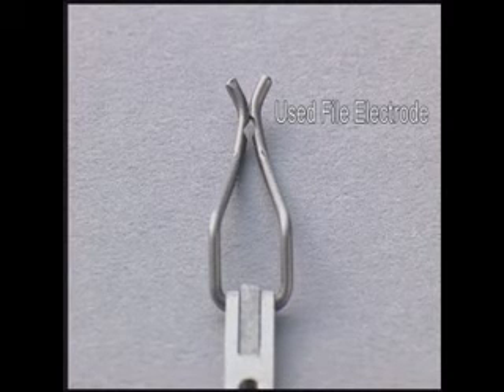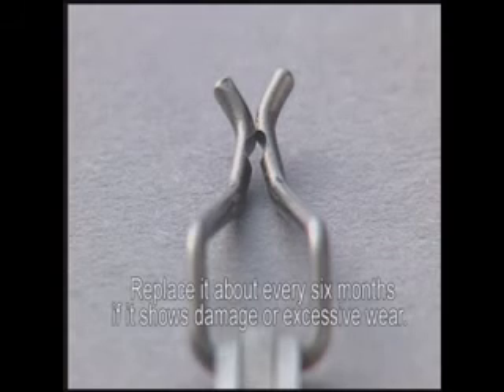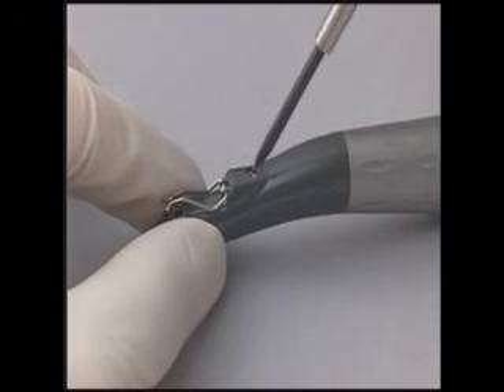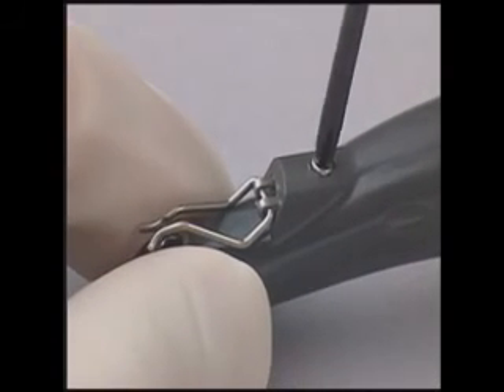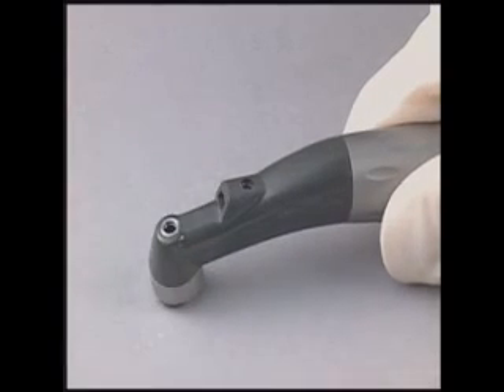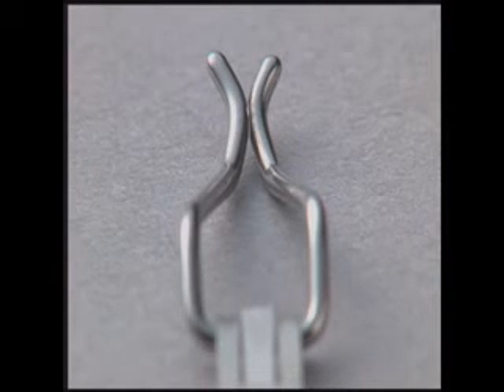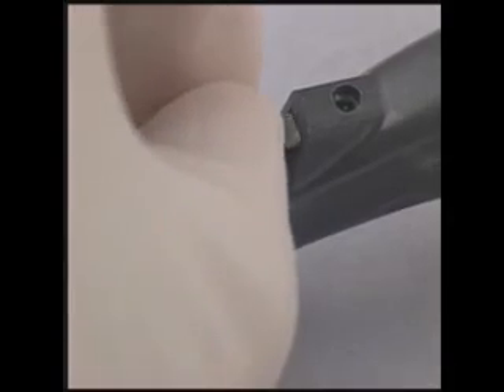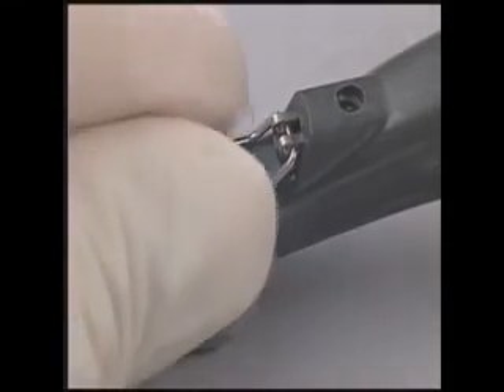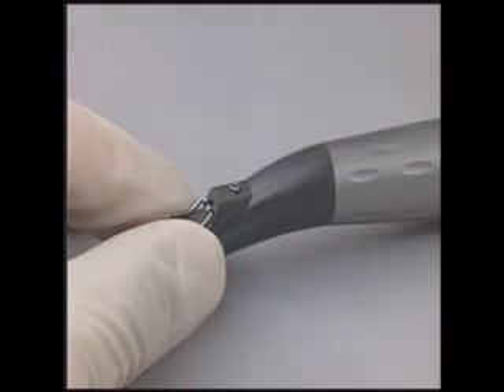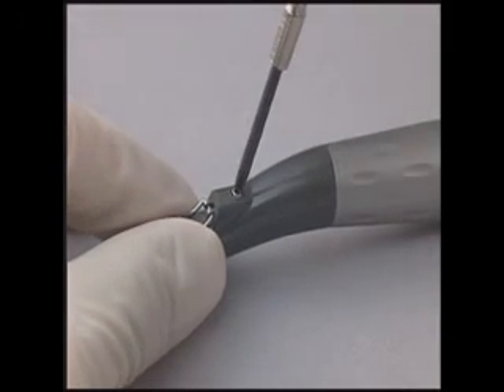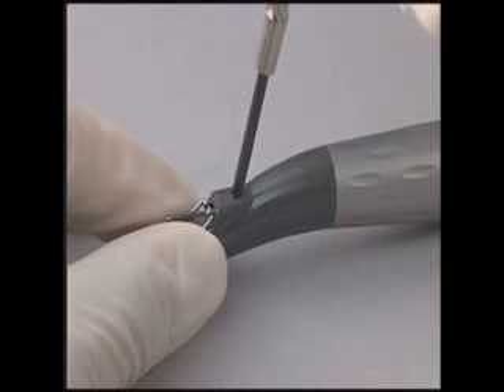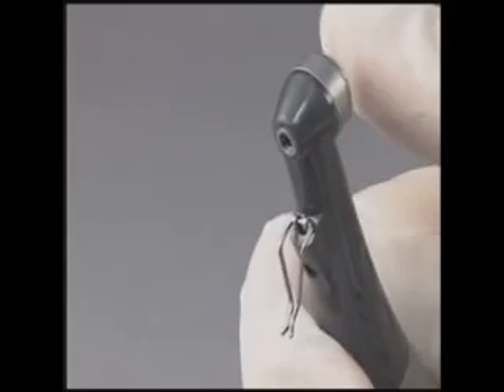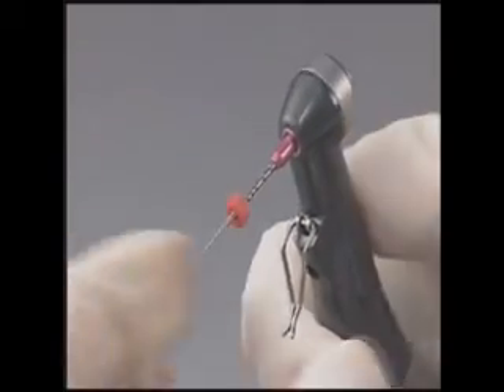An accurate measurement cannot be made if the file electrode is worn down by prolonged use. Replace it about every 6 months if it shows damage or excessive wear. Remove the file electrode's retaining screw. Pull the old file electrode straight out and replace it with the new one. Replace the screw and tighten it. Check that the new file electrode properly clips onto a file.